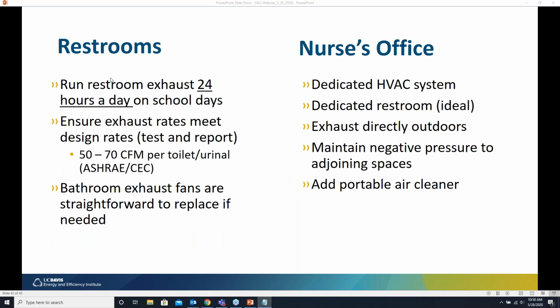Finally, make sure to pay attention to your restrooms. You should be running your restroom exhaust for 24 hours a day. You should have 70 CFM of exhaust per toilet. And also you want to test these ventilation systems as well and make sure that they're working. And bathroom exhaust fans are fairly straightforward replacements if needed.